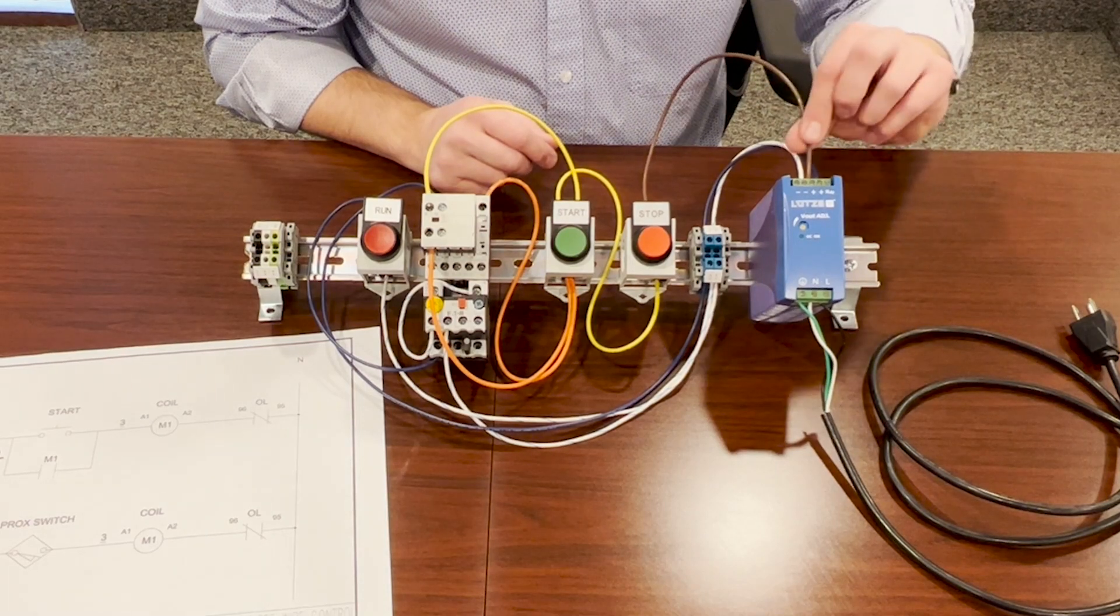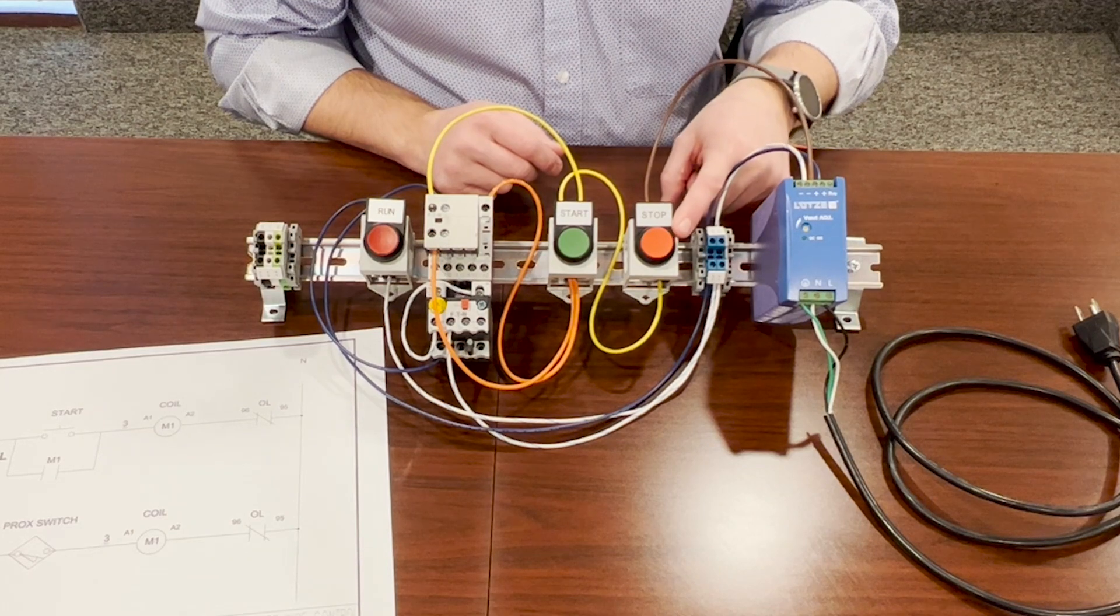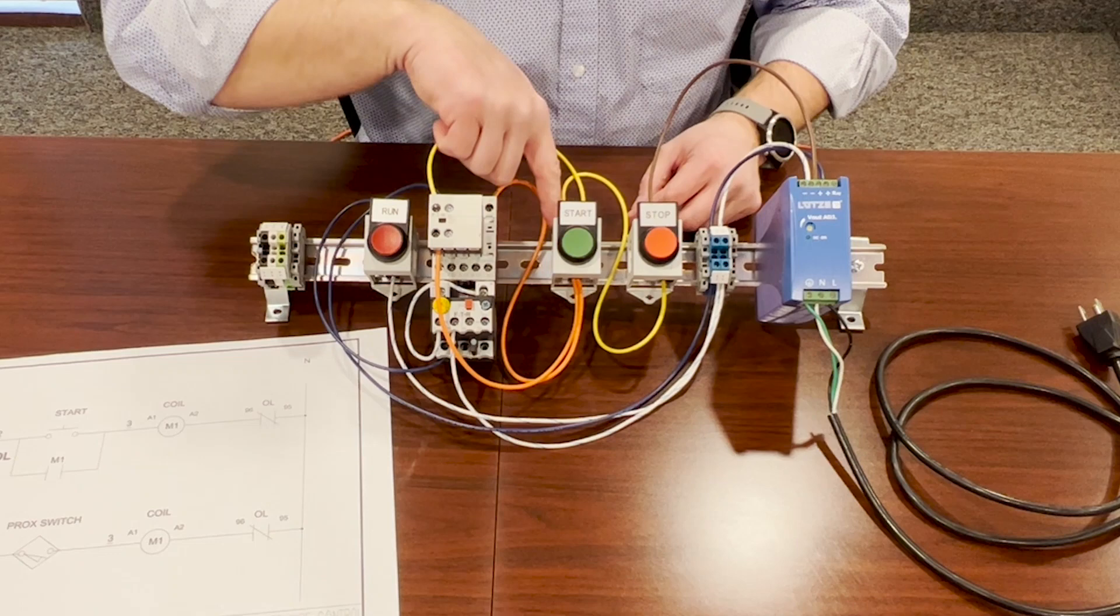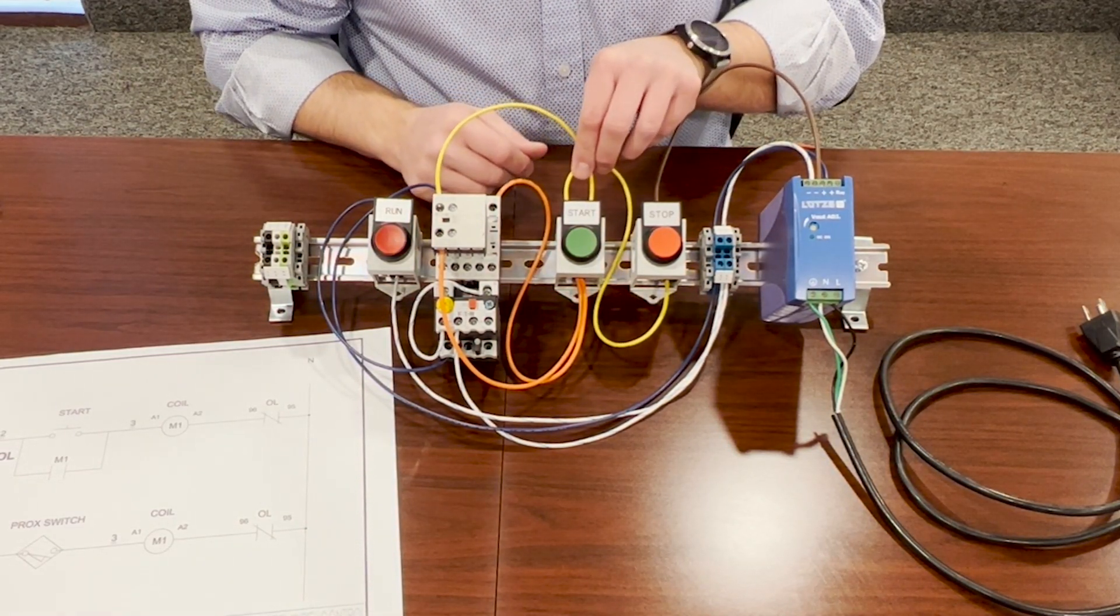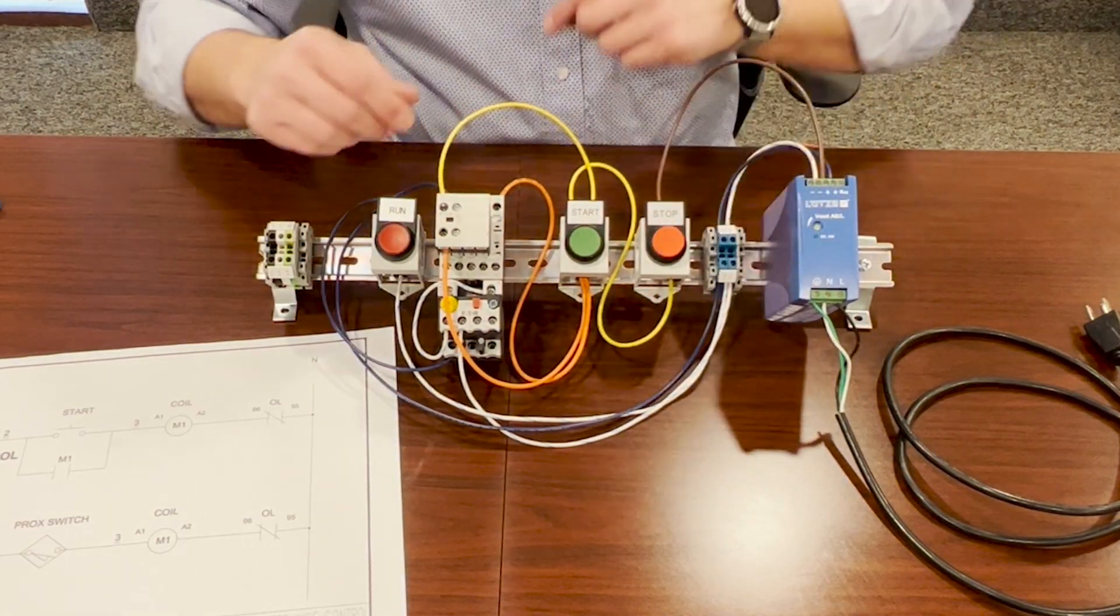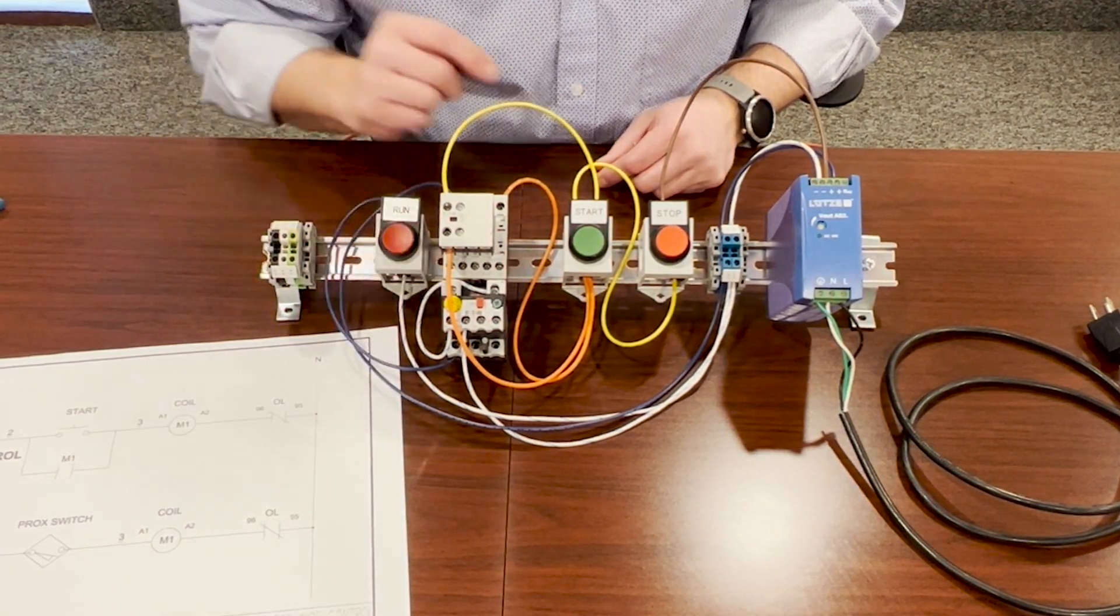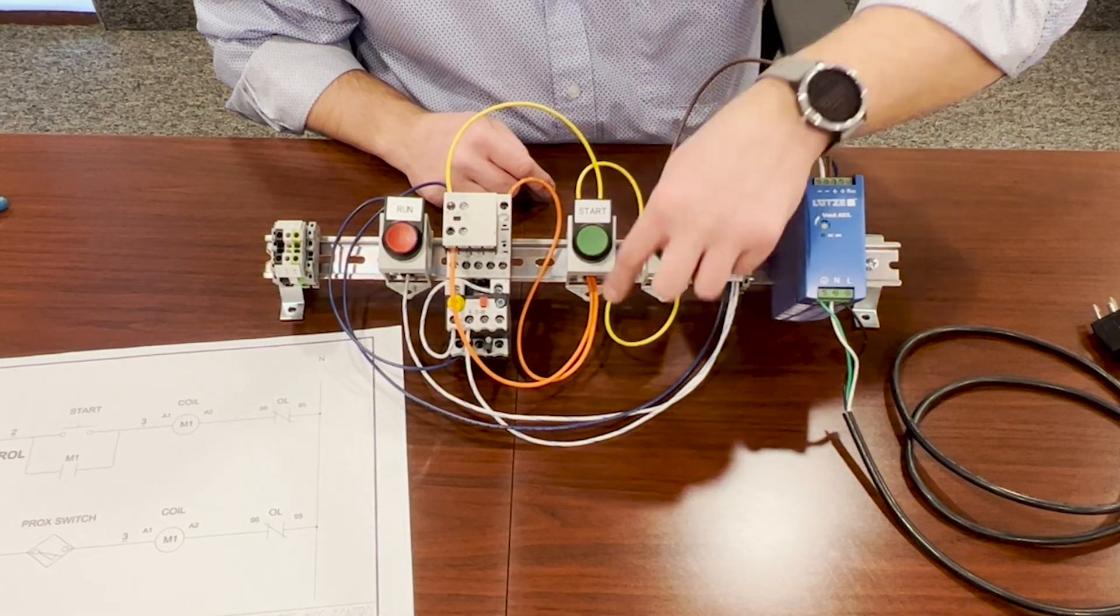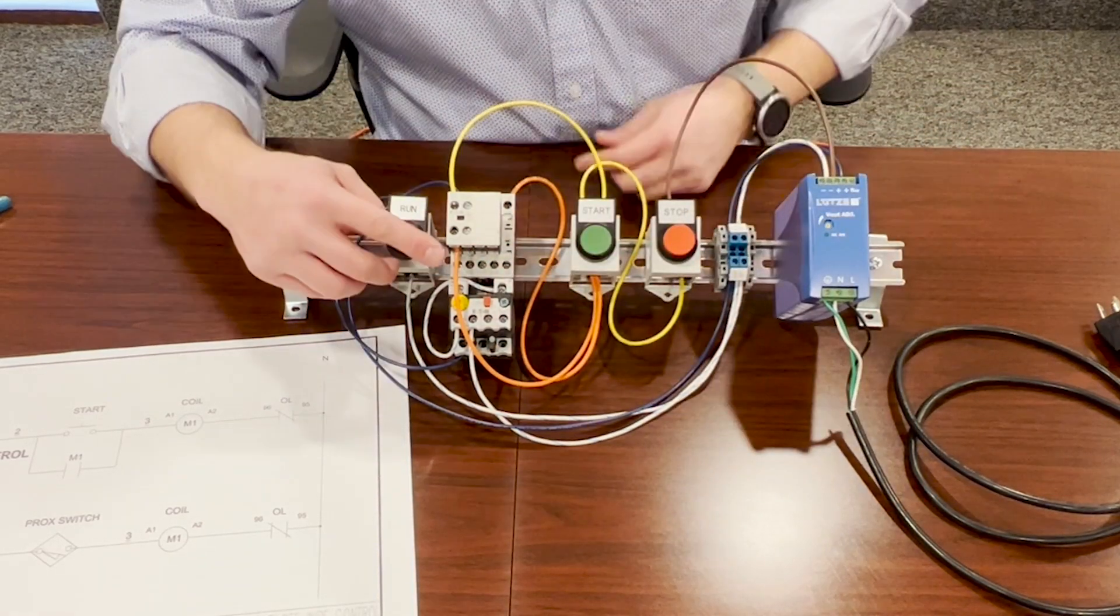So our 24 volts is going to come out of the power supply, and it's going to go to our stop button first. Normally closed contact. From there, it's going to come around to the start button, and from the start button, it actually goes two places. One, on the top of the start button, the same 24 volts that's coming from the normally closed contact here, is going to go up to our normally open contact on our motor starter. And then off of the other side of the normally open contact on the starter, it goes to the coil on the motor starter and up to the auxiliary contact.